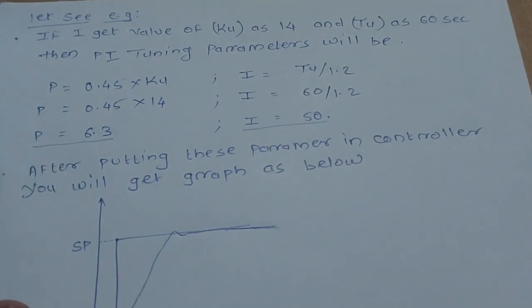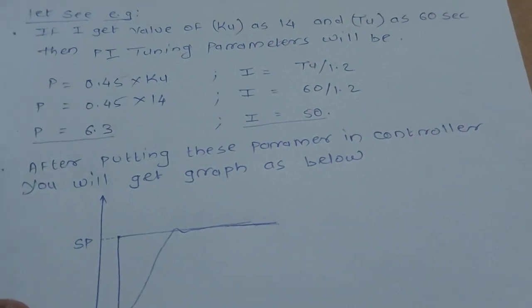The final value of P, that is proportional, will be 6.3. Similarly for I, the integral value will be Tu divided by 1.2, that is 60 divided by 1.2, so it will be 50.